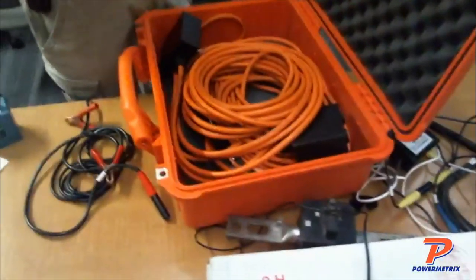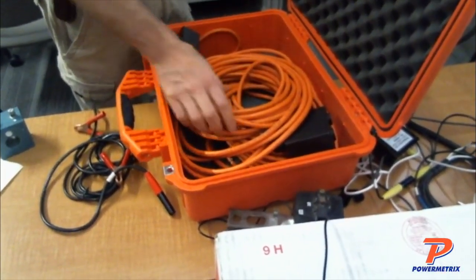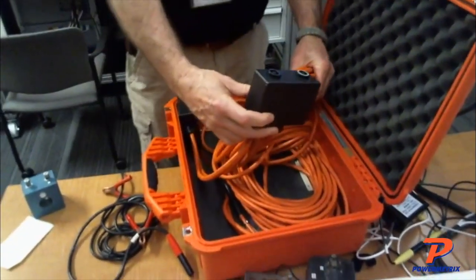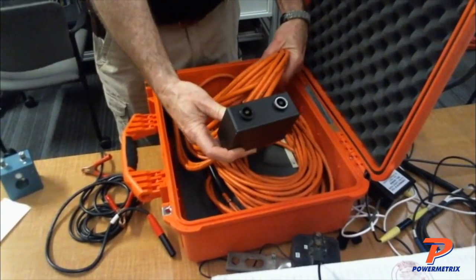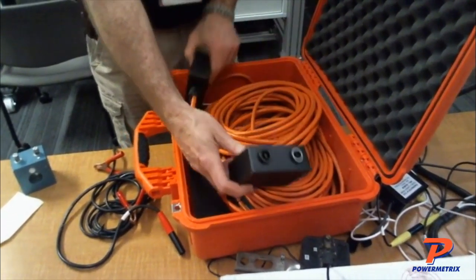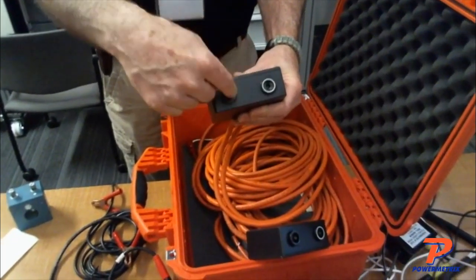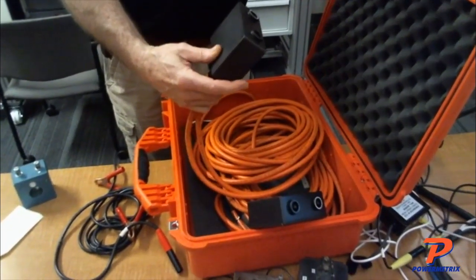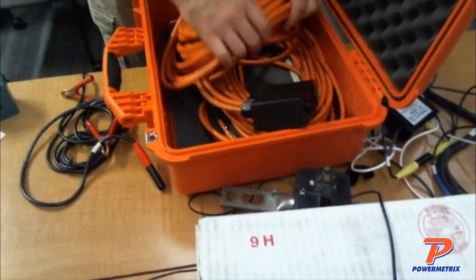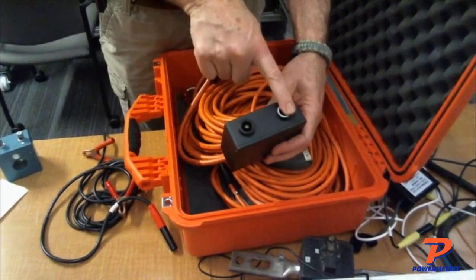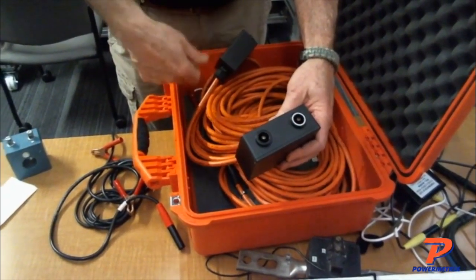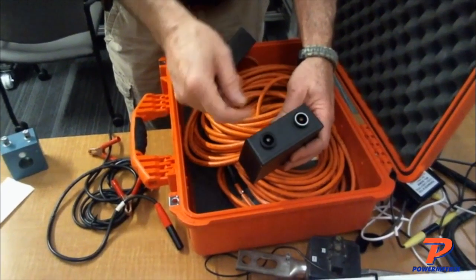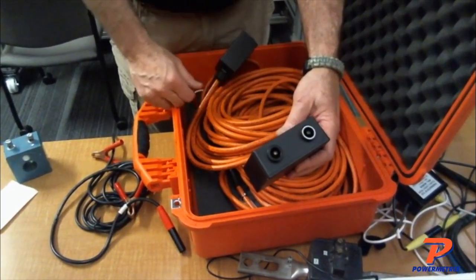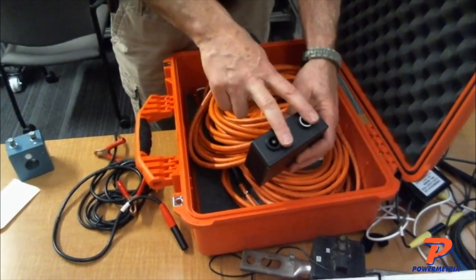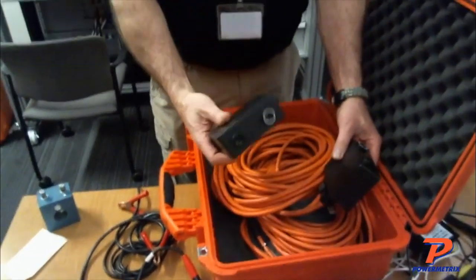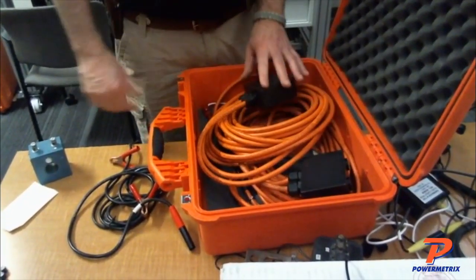So we talked about, you saw on the slides earlier, the extension we were talking about. Here's the extension to get up there. The reason we did this was to make it a lot simpler to do overhead load boost tests. With this, I just take that 6 millimeter and stick it in here and here down at the ground at the test kit. Then I can go up 20 feet in the air and run that last bit through the CT and just plug it in here and here, so I'm not running 20, 25 feet through the CT. We have this on the other end too, so when you go up in the bucket, you can run that last bit through there and connect it right here. We have a 10 foot that can go in here, 50 foot that can go in here, so we can get up pretty high. This allows you to avoid feeding all that cable through there. You don't have to do that, okay, so that's why we did it that way.